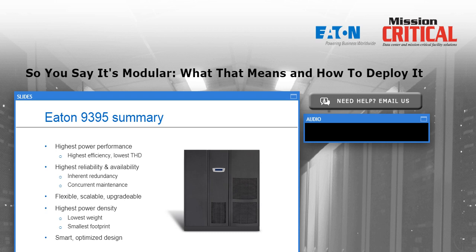The problem with oversizing a UPS traditionally, that philosophy that says, hey, I'm going to start out with a giant UPS system and not worry about, do I have enough power, do I have enough cooling, for example, I put it all in on day one. And it may take 10 years to grow into that capacity. The problem with over-provisioning like that is traditionally UPSs did not run very efficiently at very light loads. And a client could go on for years at 20%, 15%, 25% load and end up wasting quite a bit of power on a long-term basis. Modern UPSs are much, much better at this. They provide excellent efficiency today at even very, very light loads.